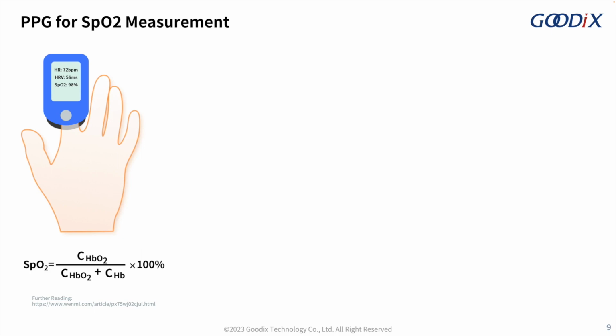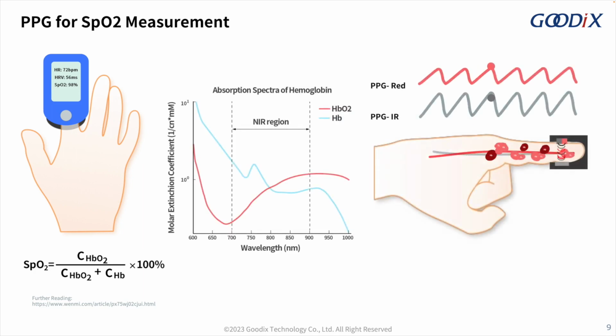Daily use of non-invasive blood oxygen measurement is also based on the PPG principle. Compared with heart rate measurement, blood oxygen measurement requires the use of two colors of light, red and infrared light PPG signals. From the absorption spectrum of oxyhemoglobin and reduced hemoglobin in the picture, we know in the red light 600 to 700 nanometer band, their absorption difference is the largest. However, the difference in absorption in the range of 800 to 1000 nanometers in the infrared spectrum is small. Using a wearable device, the AC and DC amounts of the red and infrared light are measured respectively. Finally, the blood oxygen saturation is obtained by calibrating and fitting A, B, and C. In engineering implementation, 660 nanometer and 940 nanometer are often used.